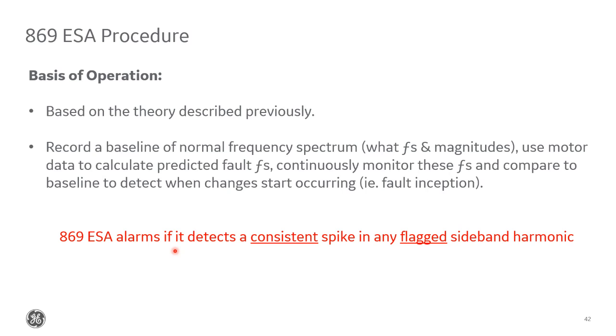We don't trip, since this is solely meant to be a monitoring element, unless you specifically set it to do otherwise. Like if you set it to operate an output contact. By default, we just provide a warning and say, hey, something's up. You need to go and take a look at the motor. And the reason for the time delay before we alarm is that we want to make sure that it's a permanent fault and not just a transient. You know, if a bearing starts to fail, it's definitely not going to fix itself. But it's not unheard of to have some momentary vibrations here and there.